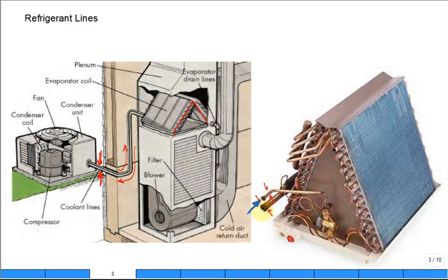So, what's coming out going back toward the compressor? Vapor. That's right, vapor. The liquid requires smaller cross-sectional area for the same mass flow rate than the vapor. The vapor has a larger specific volume or lower density, and it requires a larger cross-sectional area. Hence, you give it a larger diameter.